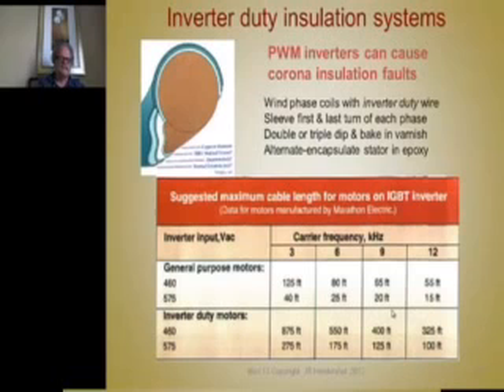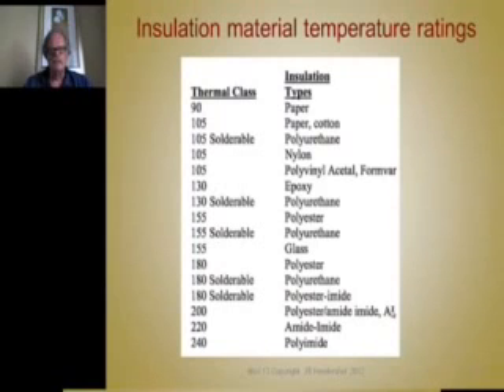The other thing that's done is to completely encapsulate the stator in an epoxy. A single layer of varnish doesn't quite do it, but another thing you can do is a vacuum impregnate system of the stator, and you can do it 2 or 3 times. That'll probably do it. Or encapsulate it in epoxy, but use inverter duty insulation wire besides. So that's the kind of caution that's taken for high performance motors with long lead wires that use PWM inverters.